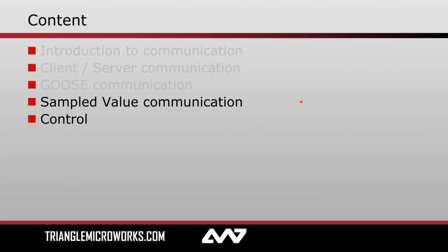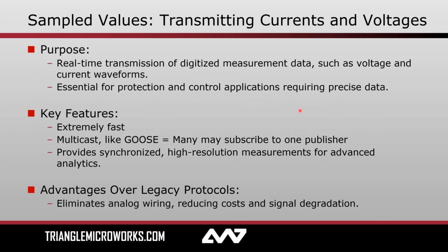Okay, so the next topic of discussion is going to be sampled values. If you guys aren't familiar, sampled values is the communication protocol that we use to transmit analog values. So think currents and voltages. In a traditional substation, we have a series of CTs and PTs, current transformers and voltage transformers, that are hooked up to different points on the line and then connected via copper wire to any IED which needs to perform some function based on those currents and voltages. Traditionally protection, but also this could be passed to metering devices, power quality, and so on.